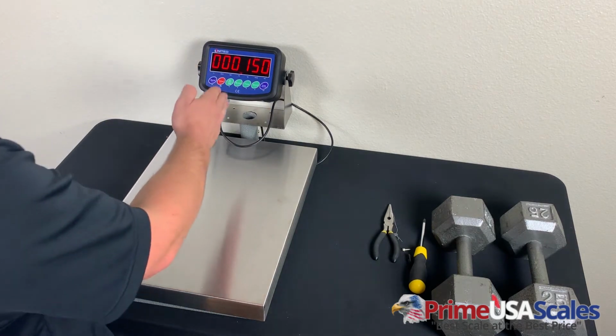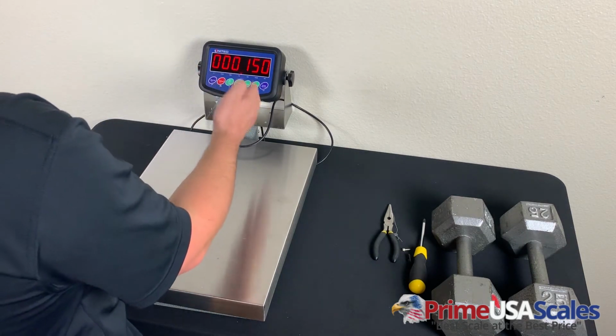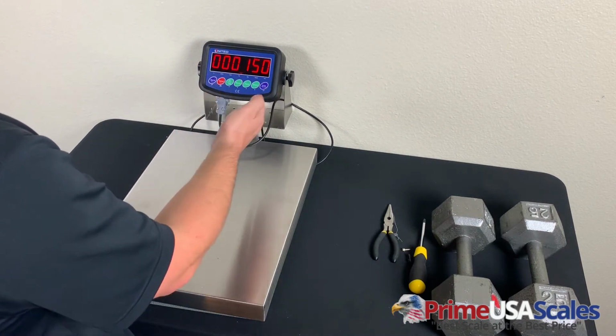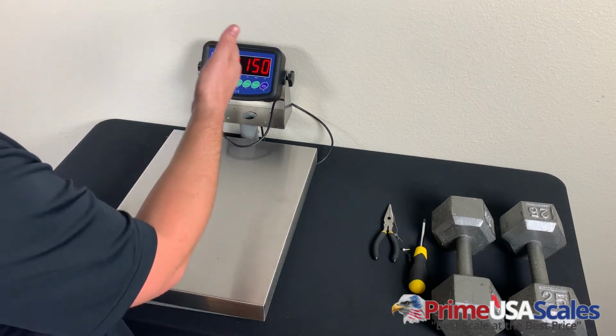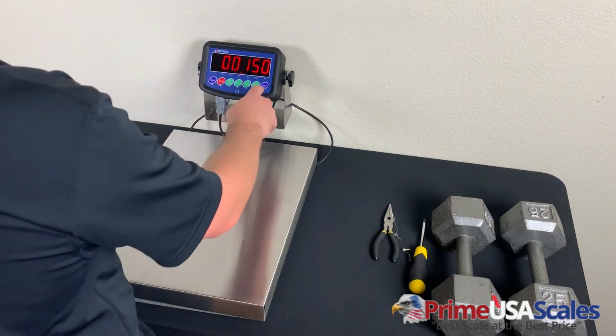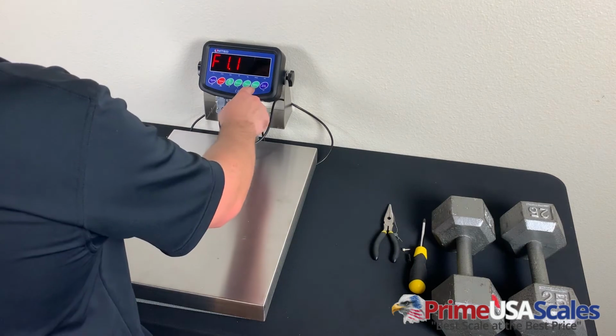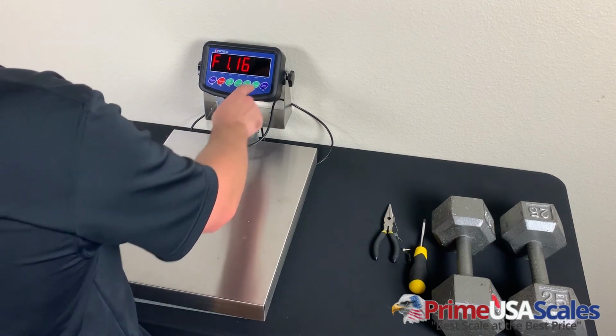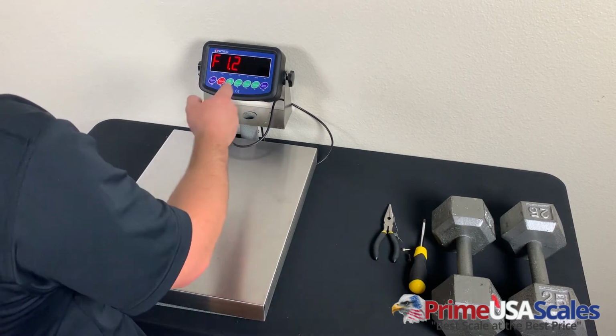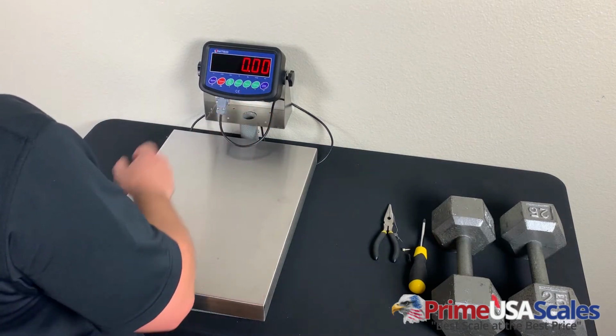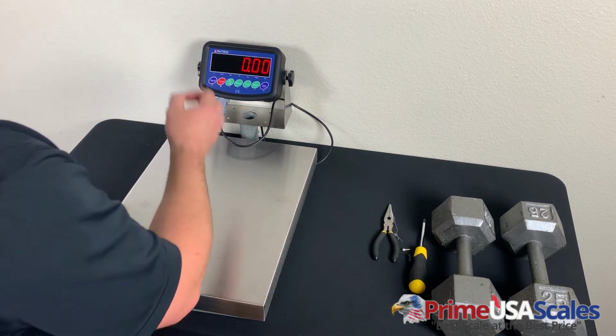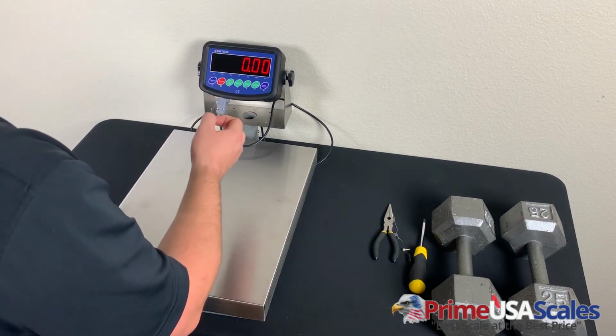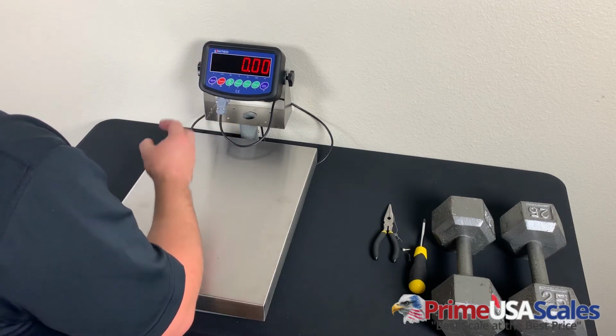Now if you want to change the capacity of the scale, it would be done in this mode here. In this case, we're going to leave it at 150 pounds because that's the default setting of the scale already. Next, we will toggle down to F1.2. This is where we'll set the decimal places. In this case, it's a 150-pound scale. We're going to have 2 decimal places set up.